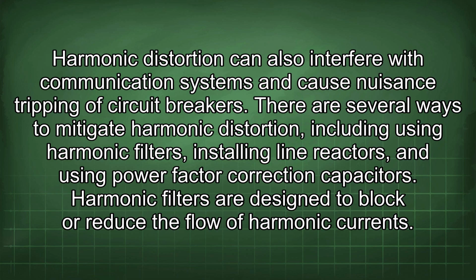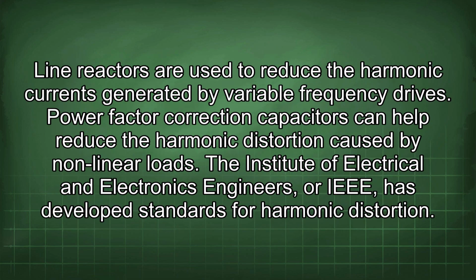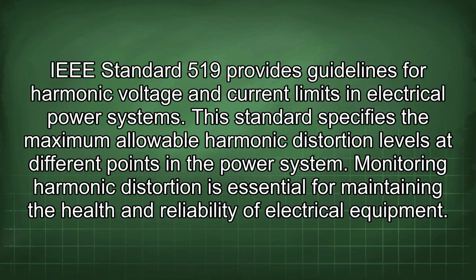There are several ways to mitigate harmonic distortion, including using harmonic filters, installing line reactors, and using power factor correction capacitors. Harmonic filters are designed to block or reduce the flow of harmonic currents. Line reactors are used to reduce the harmonic currents generated by variable frequency drives. Power factor correction capacitors can help reduce the harmonic distortion caused by nonlinear loads. The Institute of Electrical and Electronics Engineers, or IEEE, has developed standards for harmonic distortion. IEEE Standard 519 provides guidelines for harmonic voltage and current limits in electrical power systems. This standard specifies the maximum allowable harmonic distortion levels at different points in the power system.